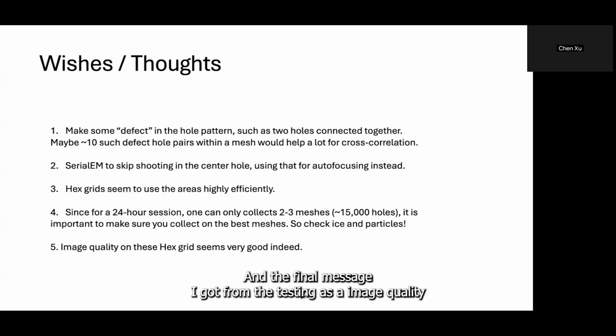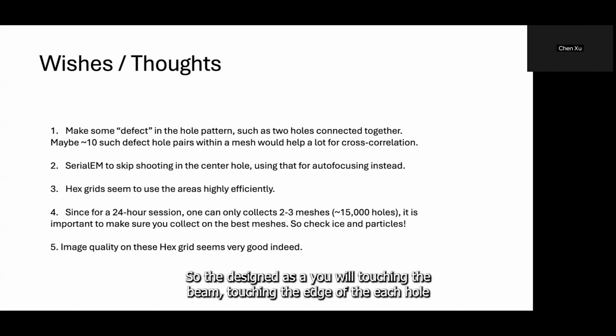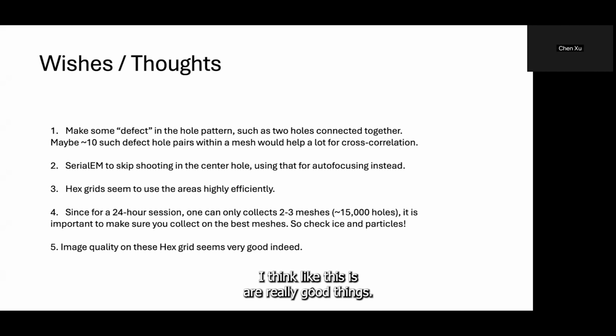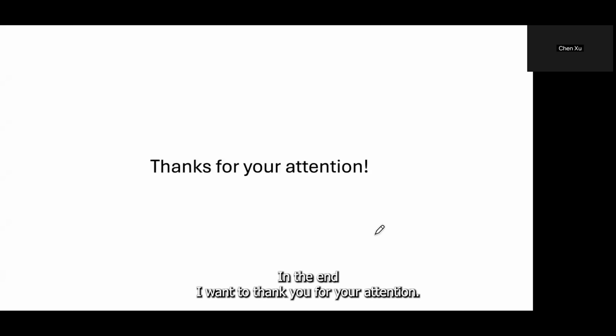And the final message I got from the testing is that the image quality is actually pretty good from Hex. We have some industry users who use all different kinds of grids, and some of the data sets they get from the Hex grids are a lot better than from other kinds of grids. I think the uniformity, the stiffness with less movement, and the design where you are touching the edge of each hole with the beam, I think these are all really good things. All right. In the end, I want to thank you for your attention.